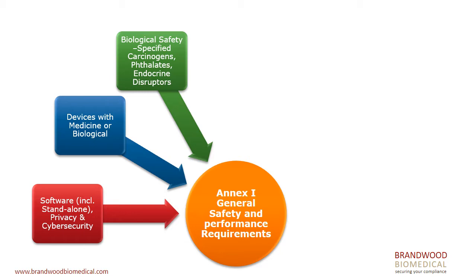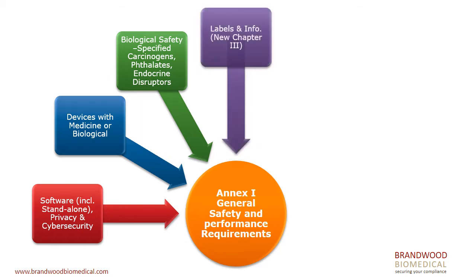Biological safety - that section is enhanced considerably. So in addition to the old basic requirements of compliance with biological safety standards largely set in ISO 10993, there's now a host of quite specific detail on things like labeling or exclusion of specified carcinogens, labeling and identification of phthalates and endocrine disruptors, and risk management to justify the presence of those substances if they are there.